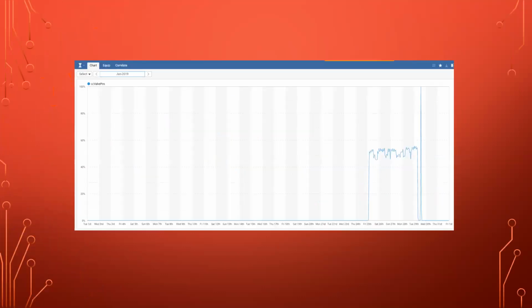So this would be another graph, an air handler that's already been commissioned. We're looking at the same thing, chilled water, the percent of the valve being open. This particular air handler, for whatever reason, in the middle of January decided it wanted to open its valve 50% on a Friday. When I came in as an energy manager on Monday and looked at this, I saw something's not right there - we shouldn't be using this chilled water right now.